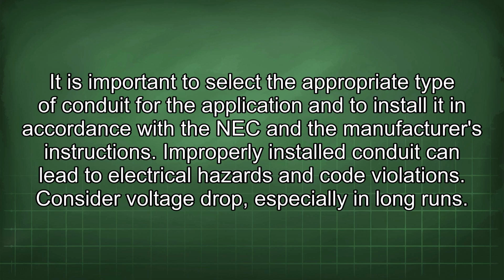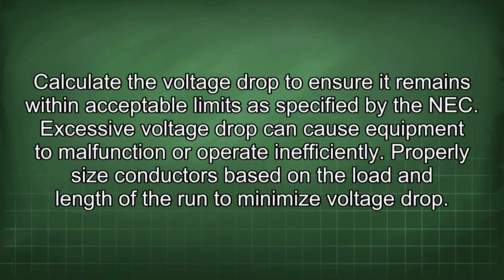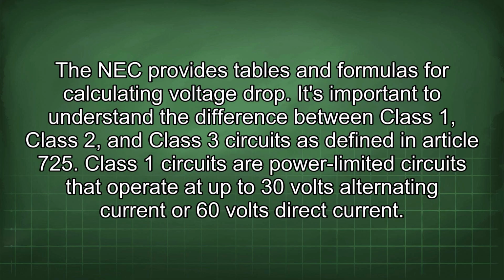Consider voltage drop, especially in long runs. Calculate the voltage drop to ensure it remains within acceptable limits as specified by the NEC. Excessive voltage drop can cause equipment to malfunction or operate inefficiently. Properly size conductors based on the load and length of the run to minimize voltage drop. The NEC provides tables and formulas for calculating voltage drop.